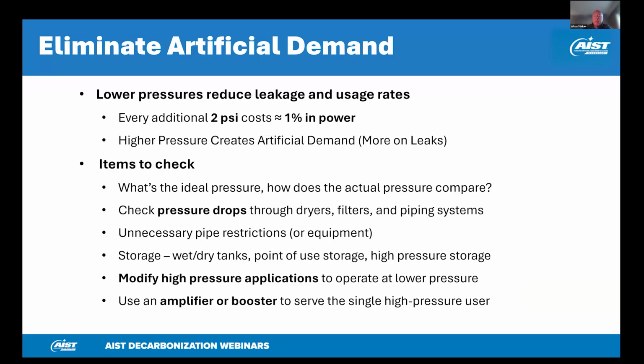The second area of opportunity is eliminating artificial demand. Artificial demand is the additional consumption of the system due to running the system pressure higher than is required. Every 2 psi that we raise the header pressure is a direct 1% increase in power required to get that pressure up. And the higher pressure creates more leaks. What's ideal pressure is important. You've got to measure and get data on what the actual pressure at the point of use is and try to control your header to that pressure.